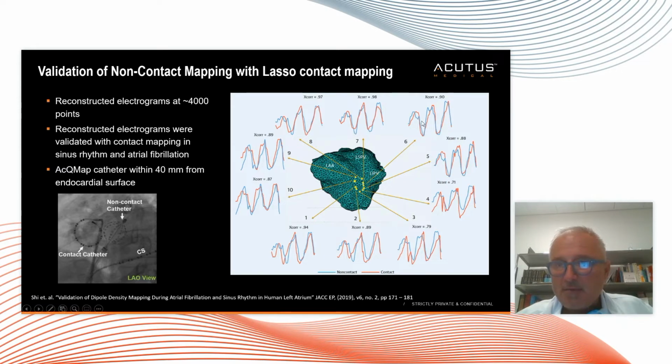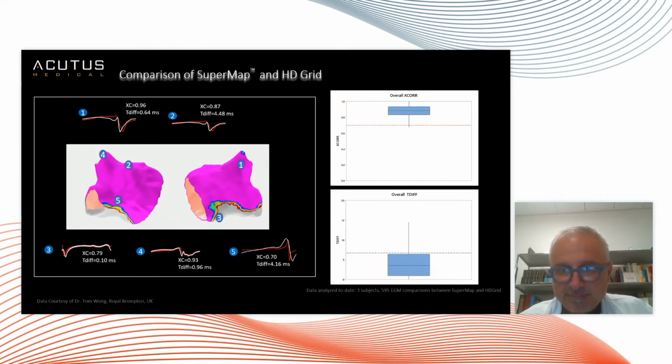And what we get with this catheter has a correlation coefficient of 0.9, 0.98, 0.97, 0.89. That's something else than 0.5, what you saw before. Also, the correlation to multi-electrodes like the HD grid is good. You see 0.9, 0.79, and the time difference of a couple milliseconds is better than the human eye.